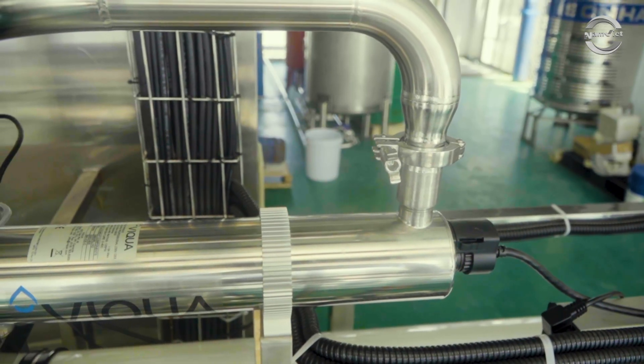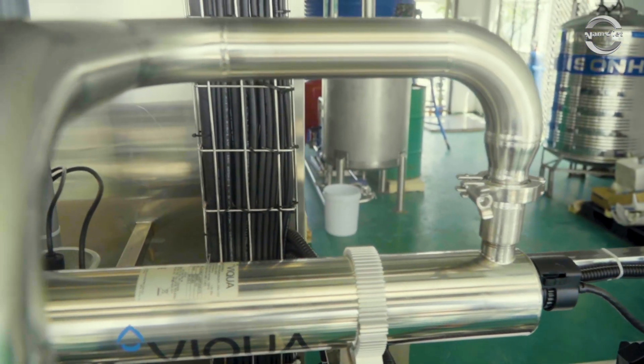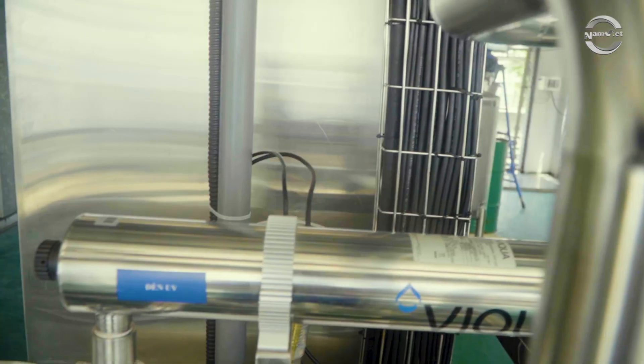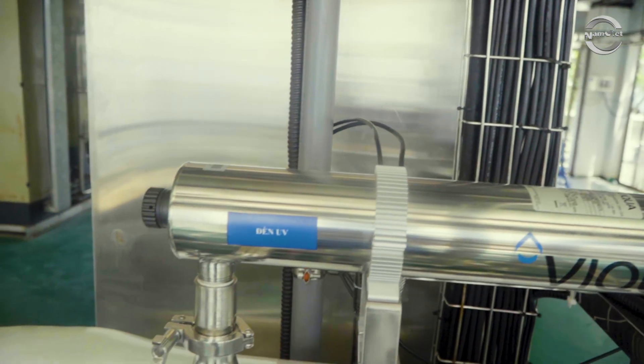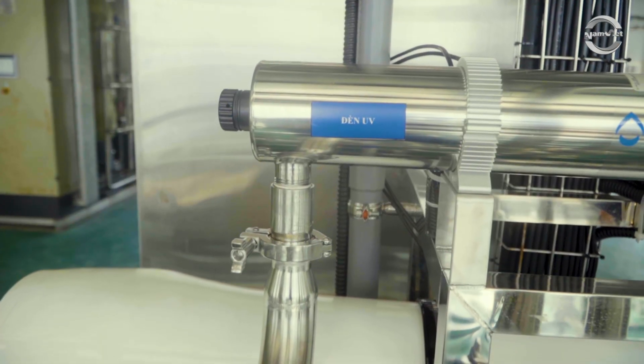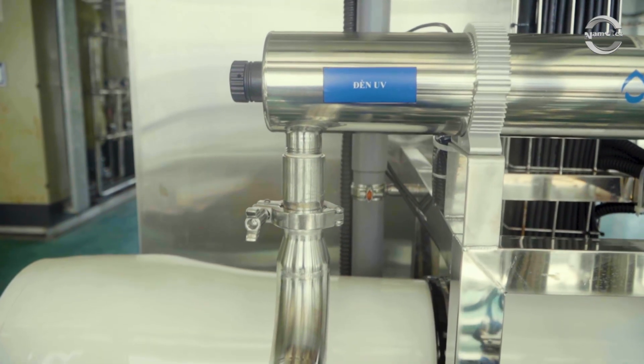In principle, water after RO treatment no longer contains harmful bacteria or viruses. However, to minimize the risk of recontamination, the water should pass through a UV disinfection lamp for additional sterilization, then through a 2 micron fine filter, also known as a post-bacterial filter, before entering the storage tank.